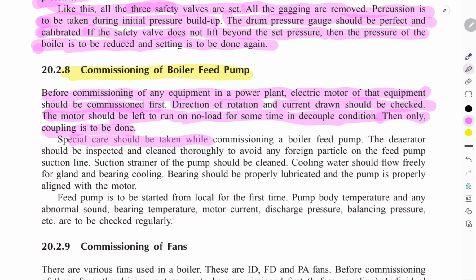Especially, care should be taken during the commissioning of the boiler feed water pump. The deaerator should be inspected and cleaned thoroughly to avoid any foreign particles getting to the feed water pump. Okay, the suction lines and suction strainer of the pump should be clean. Cooling water should flow freely for gland and bearing cooling. Bearings should be properly lubricated, and the pump should be properly aligned with the motor.